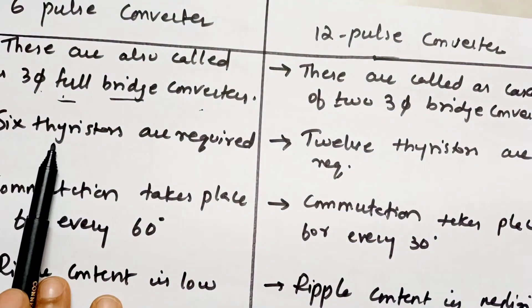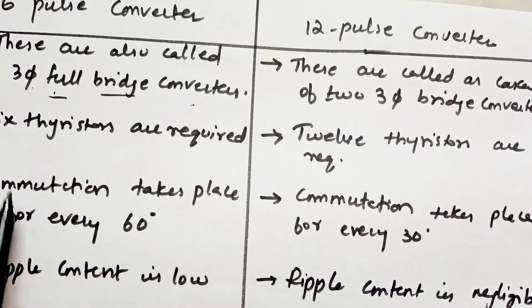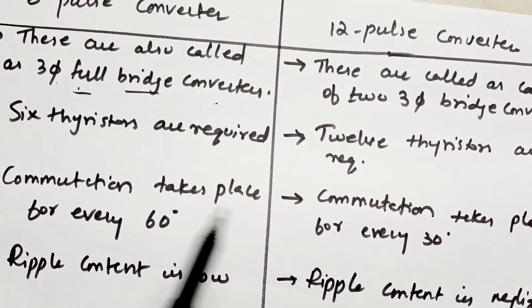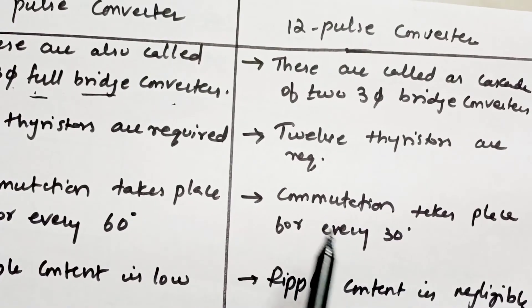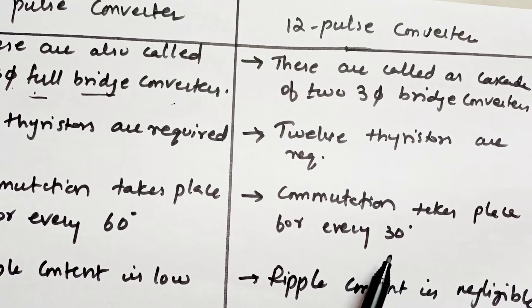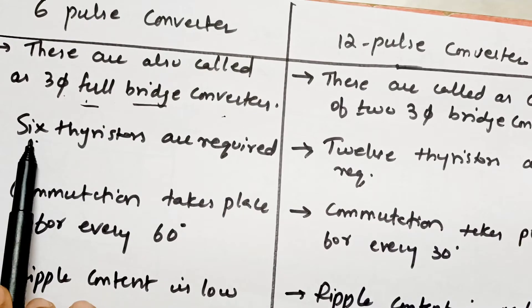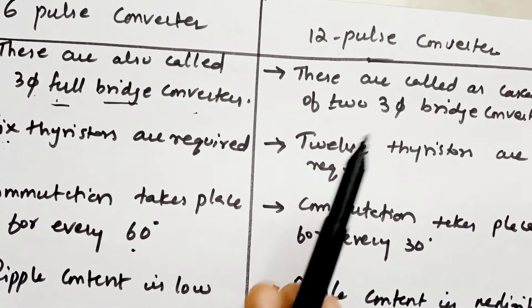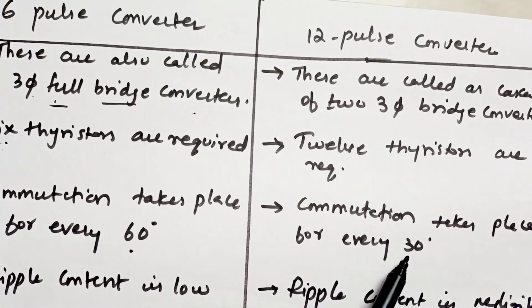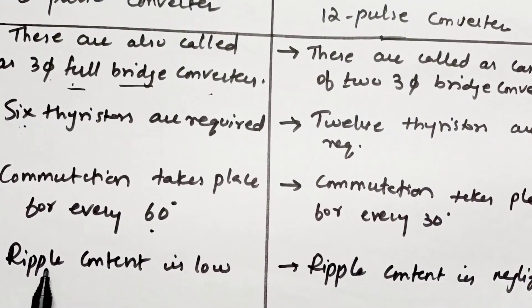In the 6-pulse converter, you use 6 thyristors, and in the 12-pulse converter, you use 12 thyristors. Commutation takes place every 60 degrees in the 6-pulse, and every 30 degrees in the 12-pulse. This makes sense mathematically: 6 × 60 = 360 degrees, and 12 × 30 = 360 degrees for a complete cycle.